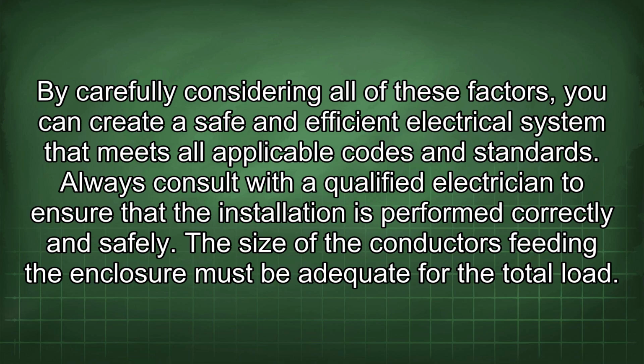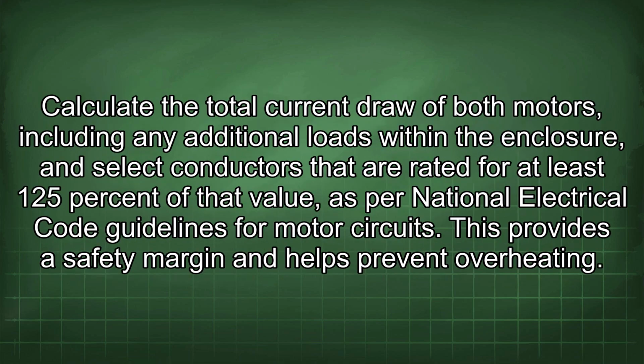The size of the conductors feeding the enclosure must be adequate for the total load. Calculate the total current draw of both motors, including any additional loads within the enclosure, and select conductors that are rated for at least 125% of that value, as per National Electrical Code guidelines for motor circuits. This provides a safety margin and helps prevent overheating.